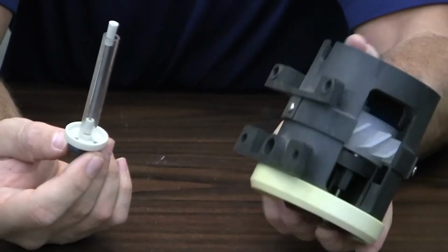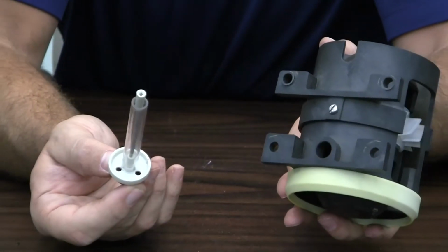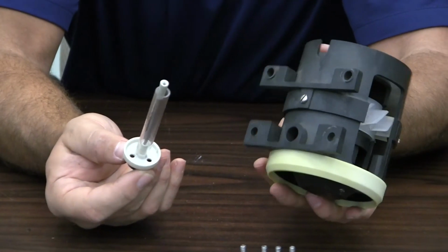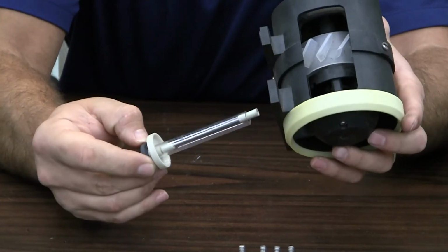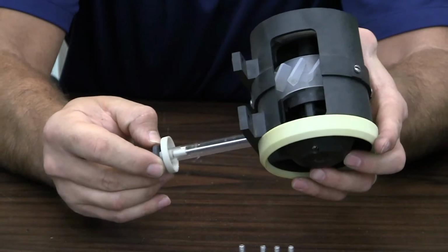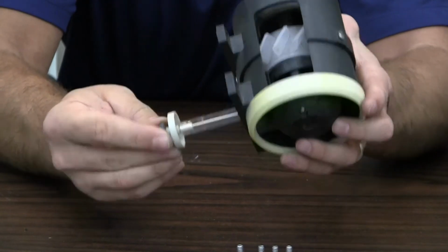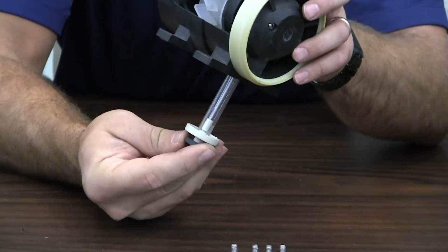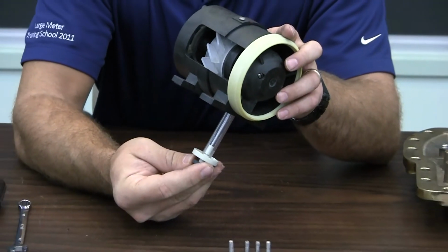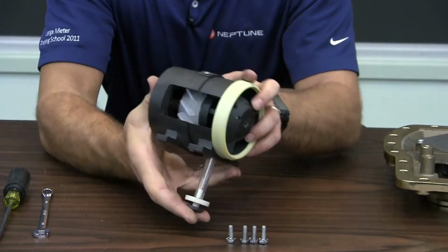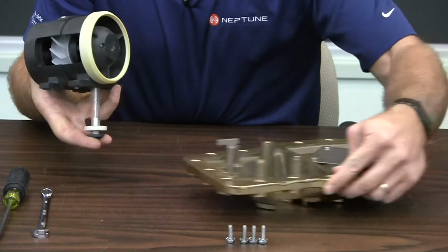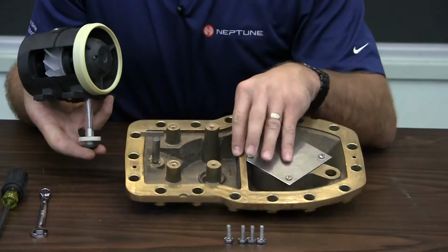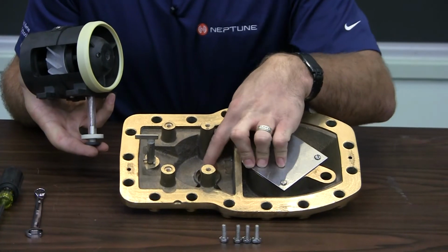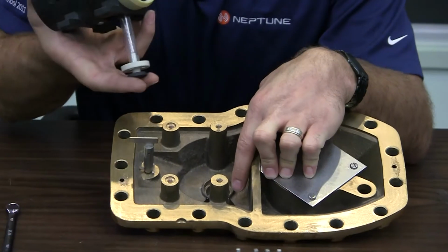To do so, there's a hole on the bottom of the turbine where the square key on the magnet coupling will lock the magnet drive to the turbine assembly. So we'll slide it up, and you'll feel it lock in. You can move the magnet back and forth, knowing that you've got an engagement between the magnet drive and the turbine assembly. To place this back in the assembly, you can see the machine magnet area where the magnet assembly will go into.